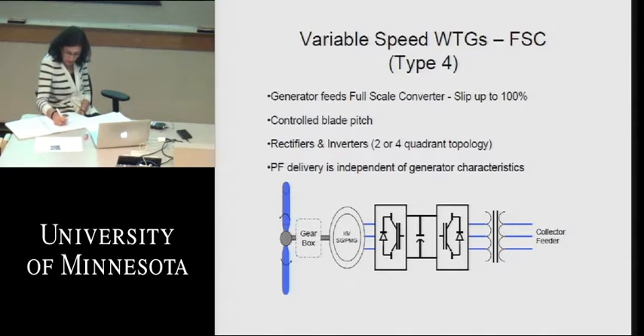But these converters are used as normal power flow would be coming out of the generator. We would use the converter with the IGBT sign there, on the generator side, as a rectifier. So we rectify that, provide that onto the DC link where you see the capacitor in the middle, and then we re-invert to AC at exactly the frequency and exactly the voltage we want to deliver to the collection grid, which connects to the outside grid. So the power factor is completely independent of any generation characteristics. So voltage control is totally affected by what we call the grid side converter.